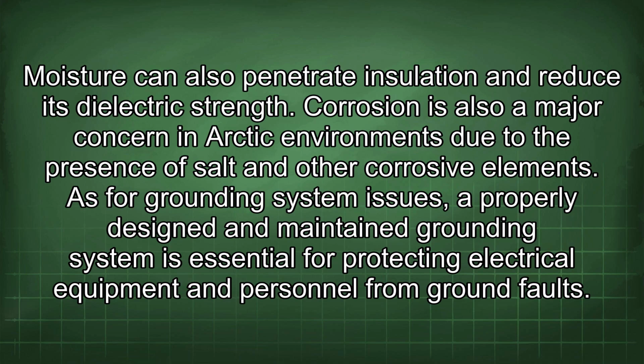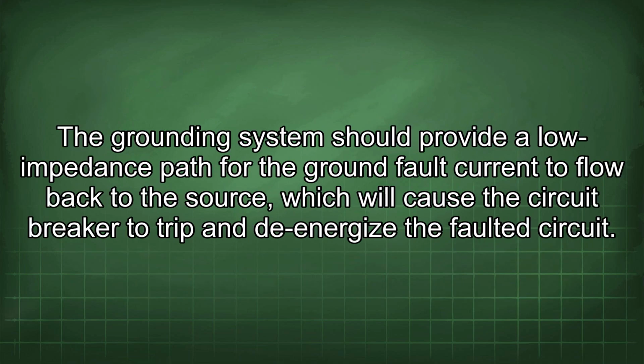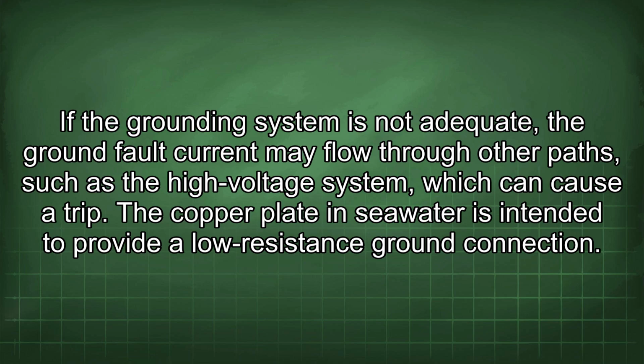As for grounding system issues, a properly designed and maintained grounding system is essential for protecting electrical equipment and personnel from ground faults. The grounding system should provide a low impedance path for the ground fault current to flow back to the source, which will cause the circuit breaker to trip and de-energize the faulted circuit. If the grounding system is not adequate, the ground fault current may flow through other paths, such as the high voltage system, which can cause a trip.